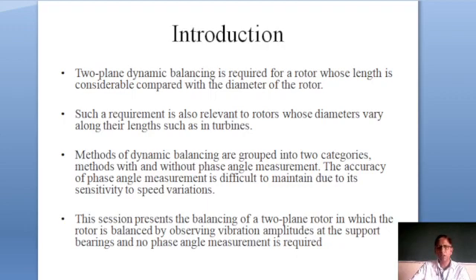Instead, this particular case study is based on the method without phase angle measurement. That means there is no requirement for dedicated instrumentation for measuring the phase angle separately. This session presents the balancing of a two-plane rotor in which the rotor is balanced by observing the vibration amplitude at the support bearings, and no phase angle measurement is required.